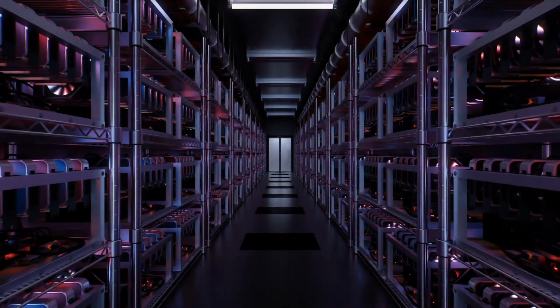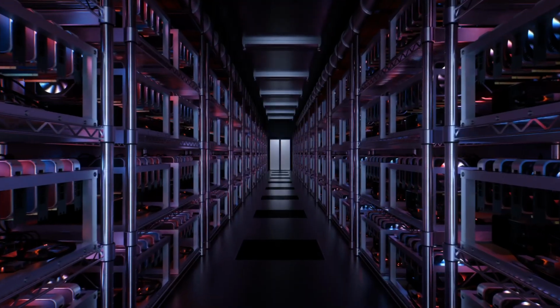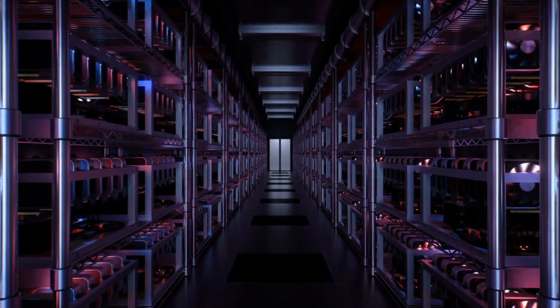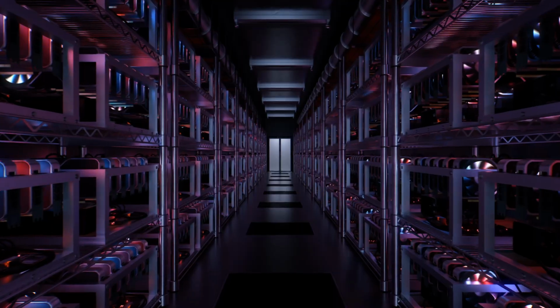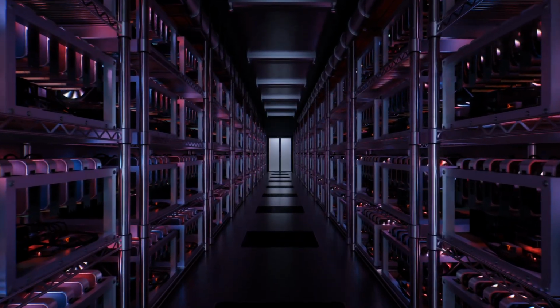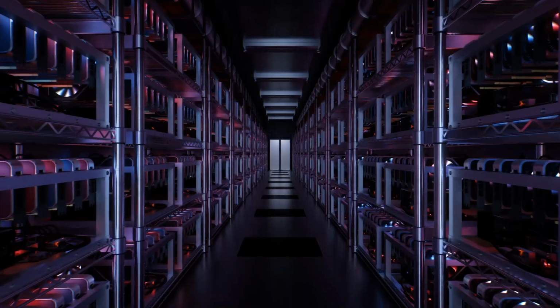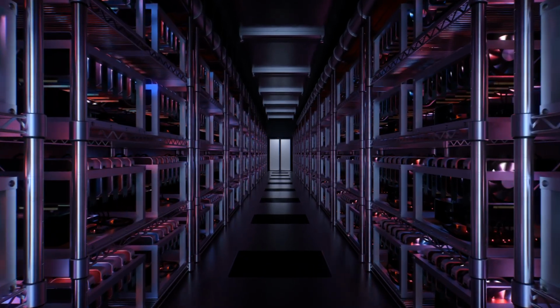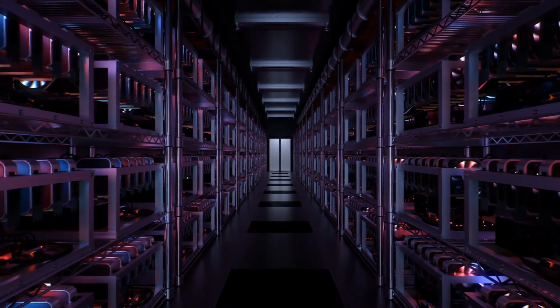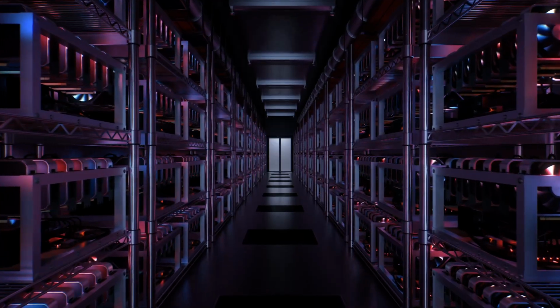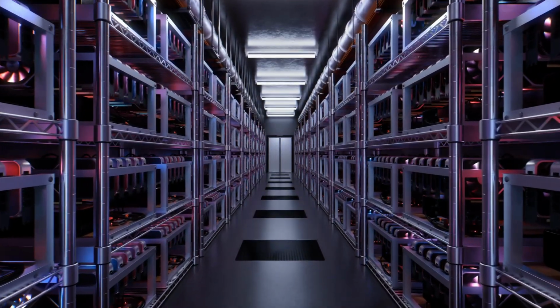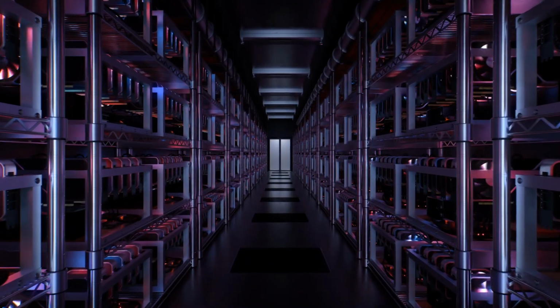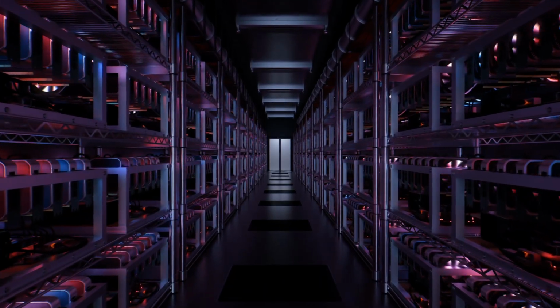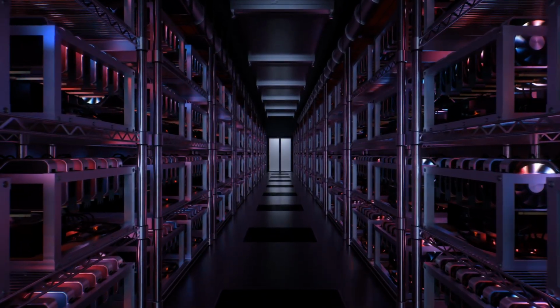And maintaining that continuous movement is so critical that the source material specifically highlights an ATS, an automatic transfer switch, for dual power sources. Because if the power to the cooling unit drops, even for just a few seconds, the servers don't just get warm, they cook. In a high-density liquid-cooled rack, if the fluid stops moving while the chips are processing a heavy AI workload, the thermal mass of the silicon will exceed critical failure temperatures in a matter of seconds.